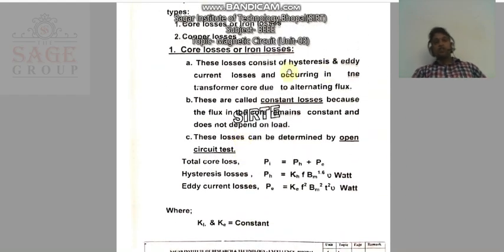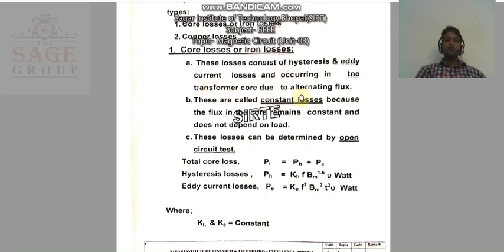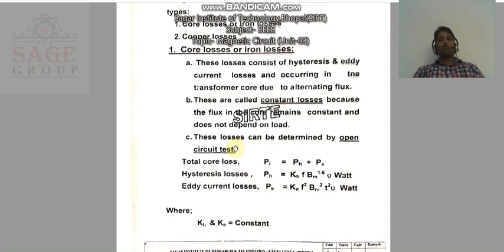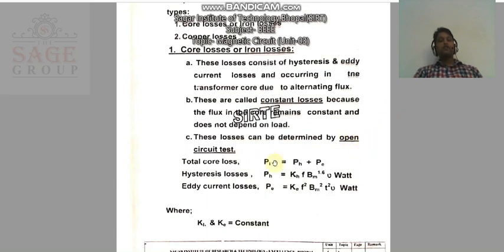These core losses consist of hysteresis and eddy current losses occurring in the transformer core due to alternating flux. They are also called constant losses because the flux in the core remains constant and does not depend on the load. These losses can be determined by the open circuit test, which we use to find out the core losses.